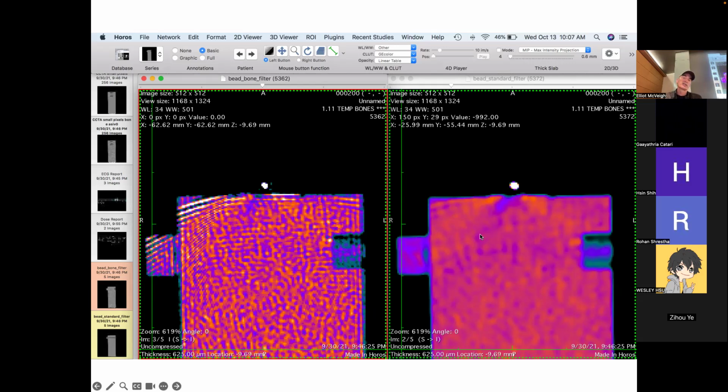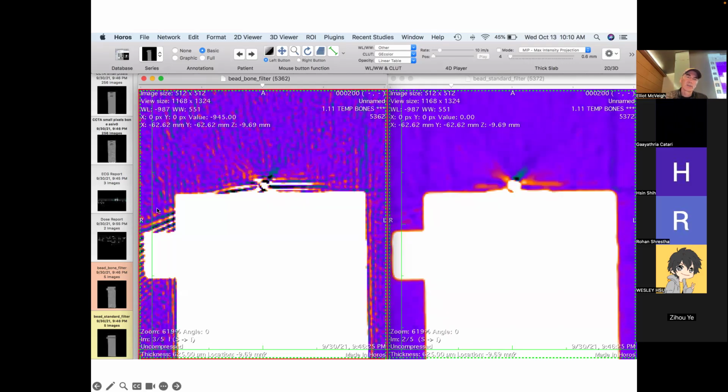And then when you use like a Hanning filter, those artifacts are diminished a lot. And so this is usually the type of filter that radiologists want to see. They don't usually want to look through this stuff. So they don't use the Ram-Lak unless they're doing something very specific. Like, I need to detect something really sharp. I will put up with the noise in order to try and find that thing. And there you can see what it's doing down at the baseline, just outside the phantom, whereas this one, all of that artifact is kind of smushed out, right?